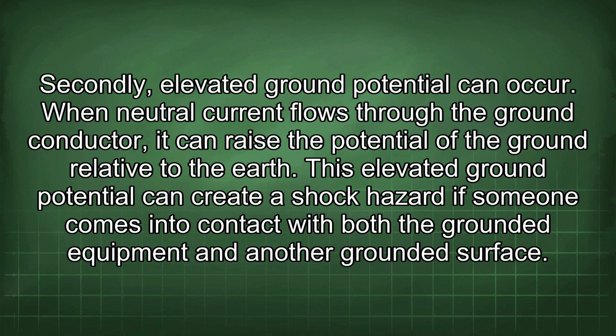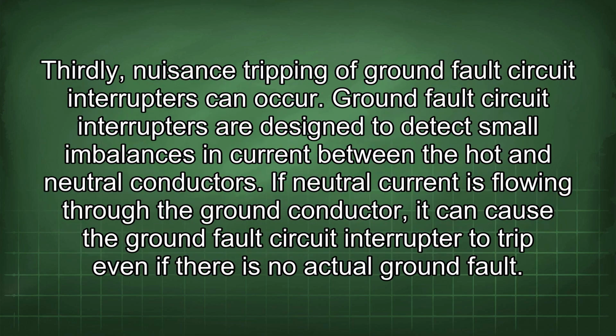Secondly, elevated ground potential can occur. When neutral current flows through the ground conductor, it can raise the potential of the ground relative to the earth. This elevated ground potential can create a shock hazard if someone comes into contact with both the grounded equipment and another grounded surface. Thirdly, nuisance tripping of ground fault circuit interrupters can occur. Ground fault circuit interrupters are designed to detect small imbalances in current between the hot and neutral conductors. If neutral current is flowing through the ground conductor, it can cause the ground fault circuit interrupter to trip even if there is no actual ground fault.